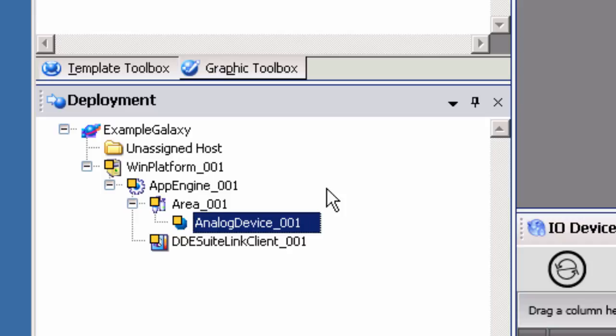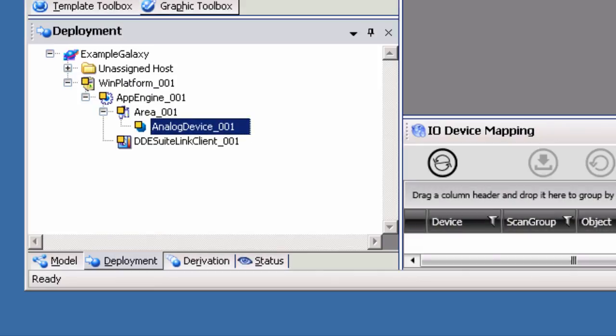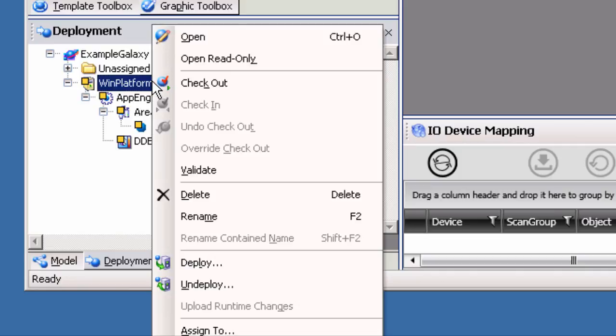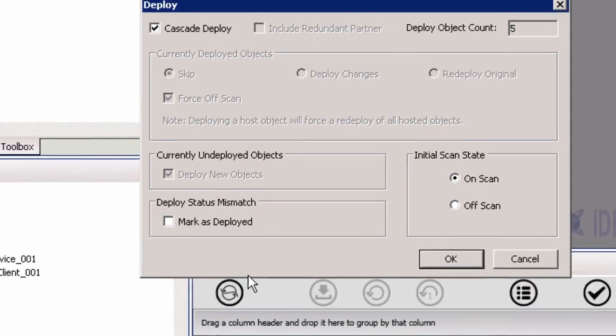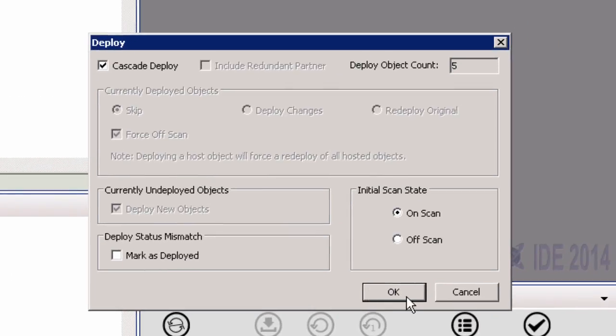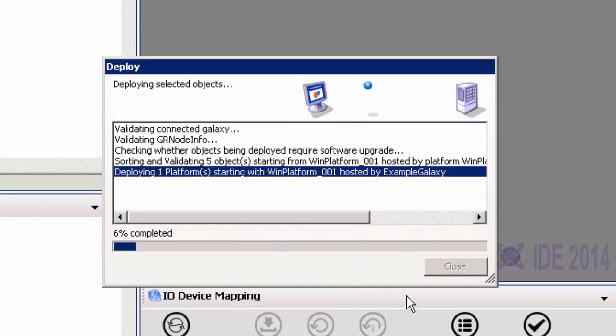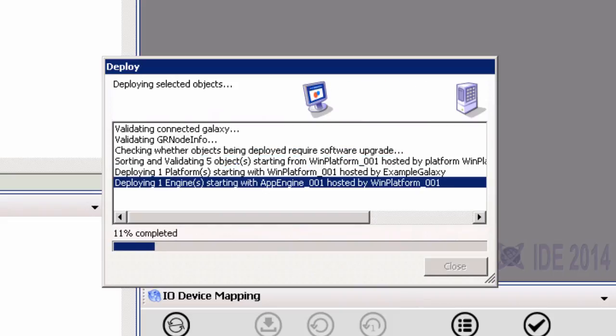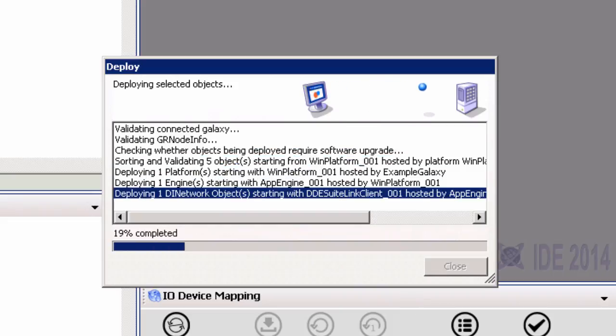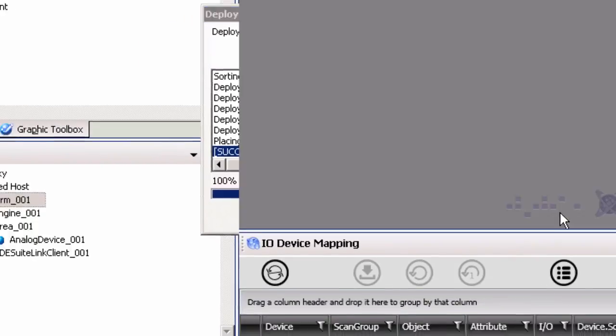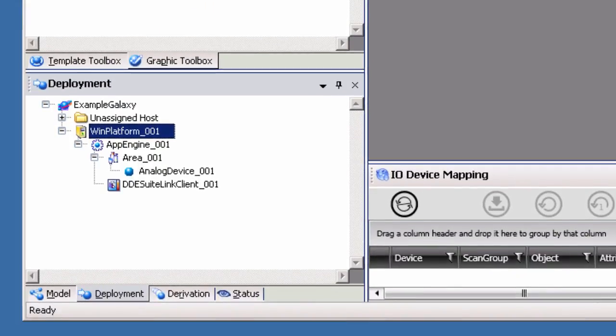Now that all objects have been created and assigned, the next step is to deploy the Galaxy. To do so, right-click on the Win Platform object in the deployment view and select Deploy. This will open the Deploy dialog box. Leaving the default settings selected will deploy all objects configured. Click OK to begin the deployment process. Once the deployment process is complete, click Close.